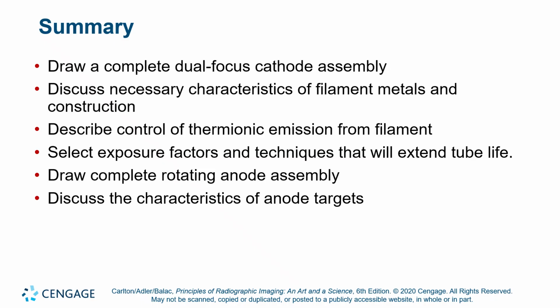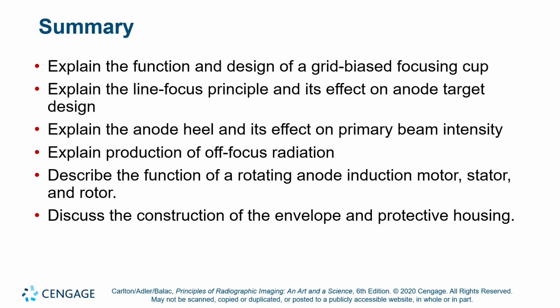Remember, the first X-ray tube was a Crookes tube, and it was only partially vacuum evacuated. It had a cold cathode, no focusing cup, and no rotating anode. And they still made X-rays with it. So that's the difference between necessary and efficiency improvements. Your modern X-ray tube has all the components present. Remember the grid biased focusing cup.